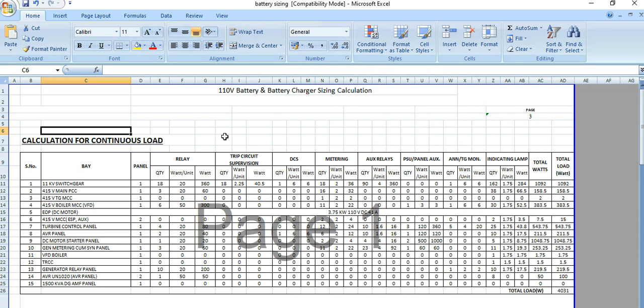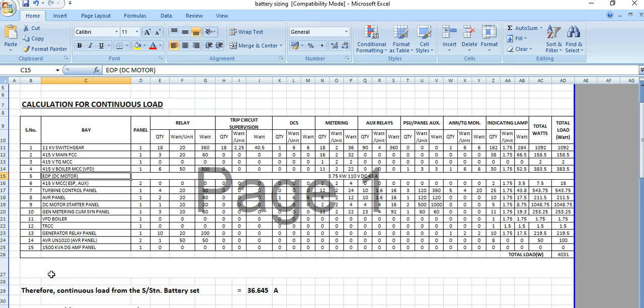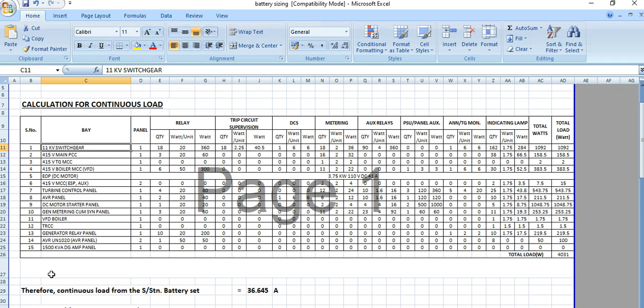The first step is the calculation of continuous load. For continuous load, we need to calculate the continuous DC supply required for the normal operating condition of all switchboards and panels. For example: 11kV switchgear, 415V main PCC, MCC, EOP DC motor (emergency oil pump), LV panel, DC motor starter panel, generator relay panel, AVR panel, DC MA panel — you need to list all continuous load requirements.